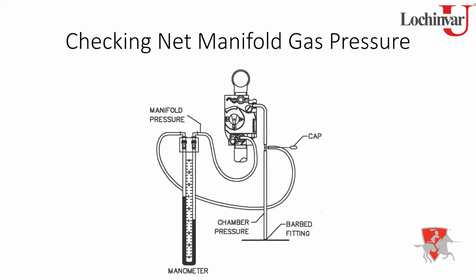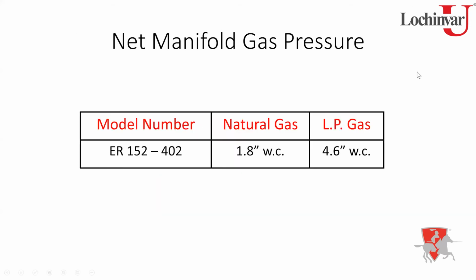Now, if you've got a single tube manometer, and a lot of people do, and that's fine, you set your deck first, then you hook up your manometer to that outlet tap, and then you fire the unit up. Now, when the valve opens, what you're going to see is what's called the gross manifold pressure. That's the pressure that the regulator is adjusted to, plus the air pressure on top of it. Let's say the air pressure on the deck is 1.4 inches. Now I'm looking for a net manifold pressure of 1.8 inches for a natural gas heater. That's what I want that regulator adjusted to.